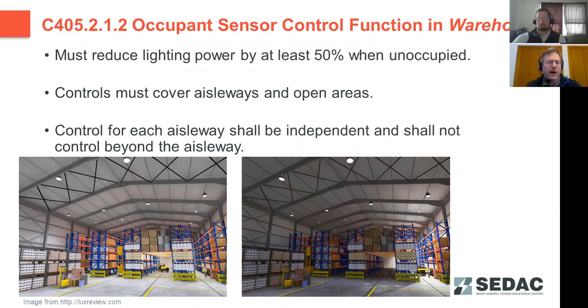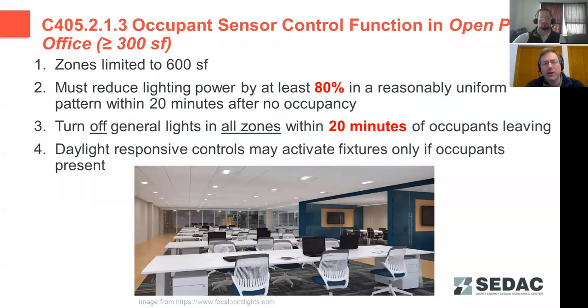Starting with warehouses, this requires at least a 50% reduction in lighting when occupancy is not detected by the occupant sensors. With this, we need to control the open bay areas, towards the front of the illustrations here, separate from our aisleways, and each aisleway needs to be independent of one another. So if we have someone picking items in one aisle, we don't need the lights on in the next aisle over from them. There are a few different thresholds that you'll see throughout this. Here again, it calls for at least a 50% reduction when the occupant sensors detect no more occupancy in that area.